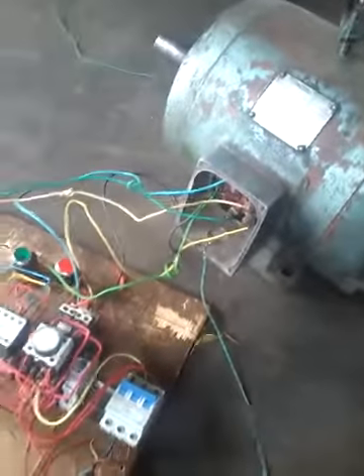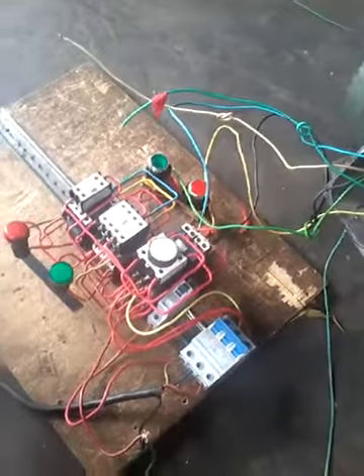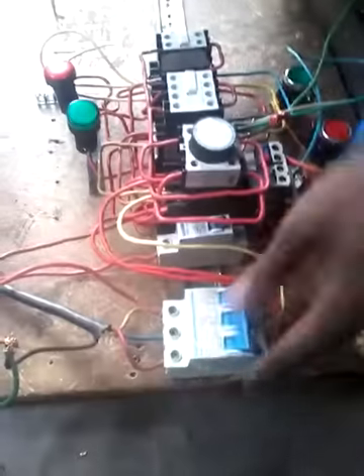I want to start this motor using a star-delta connection, so that's the tutorial today. We're just following this diagram here. As you can see, our motor is getting the power from the delta — this is the star — that's the same with what is here.